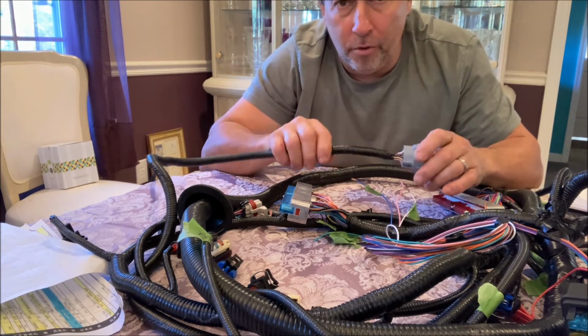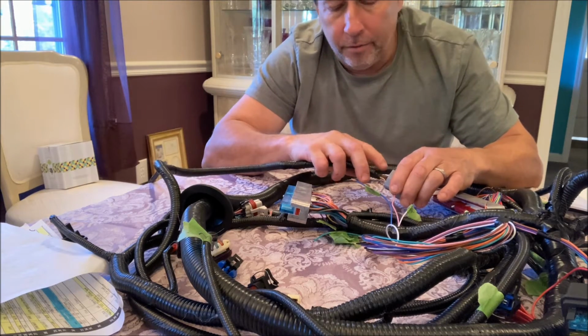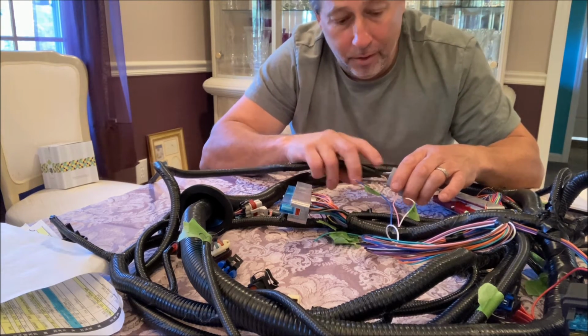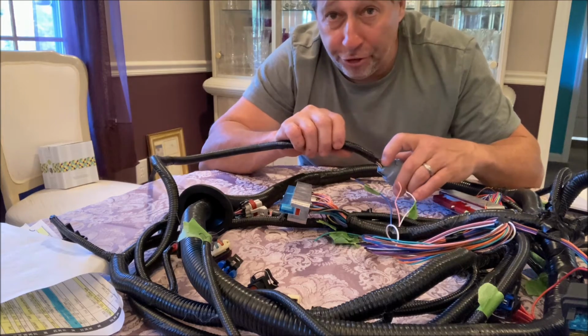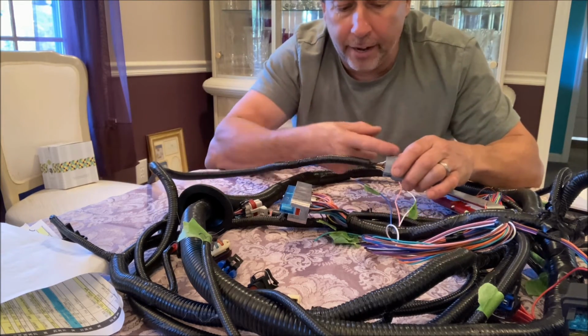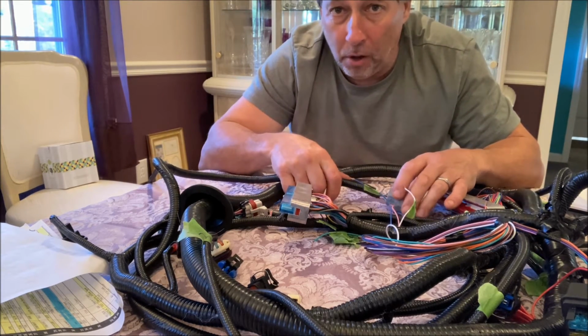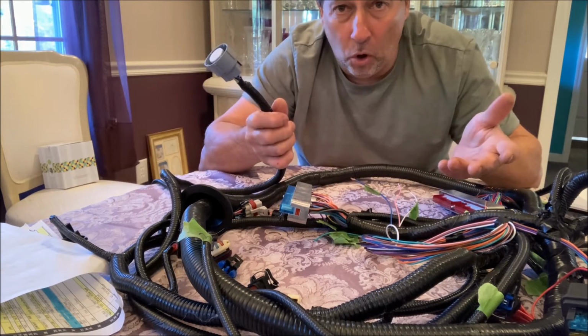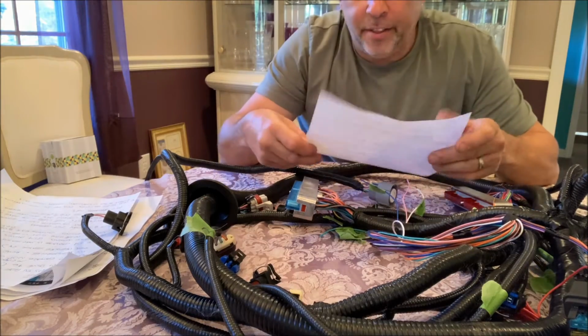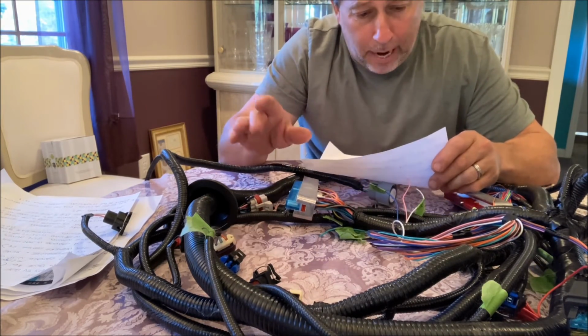So I had to remove the brown wire from the S position and move it over to U where it belonged, and connect the white wire in S where it belonged. After that, golden, no issues. So that's one thing that was manufacturer error. Absolutely.